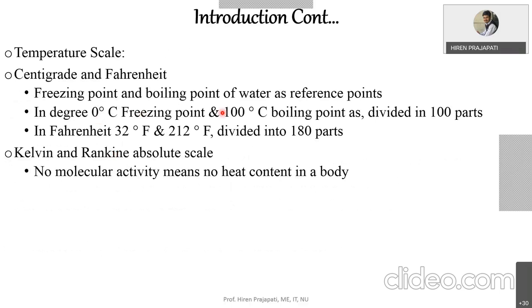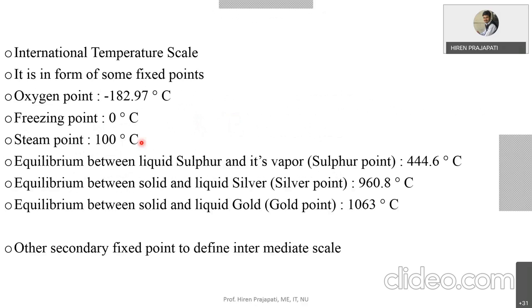While we have considered two popular reference points, for other reference points we use different equilibrium phases between liquid and vapor of different materials. For example, liquid sulfur and its vapor temperature is 444.6 degrees Celsius. Silver converting from solid to liquid occurs at 960 degrees Celsius. Gold temperature is also used as a reference. These are other reference points used for preparing the scale of instruments for temperature measurement.